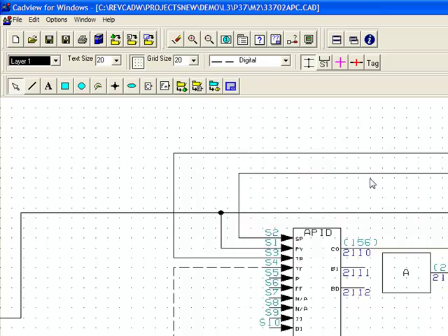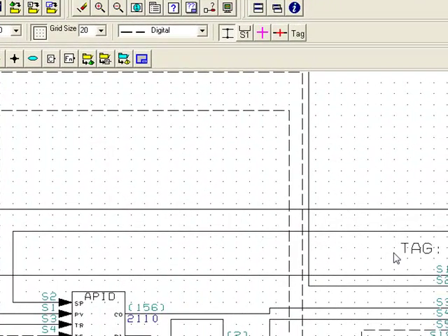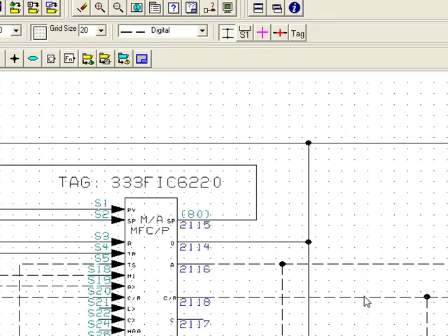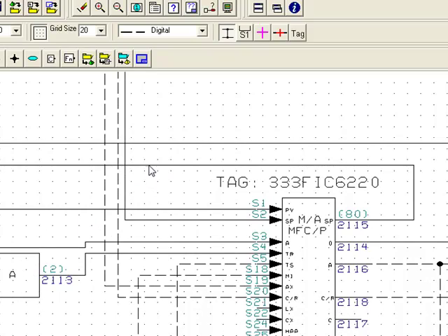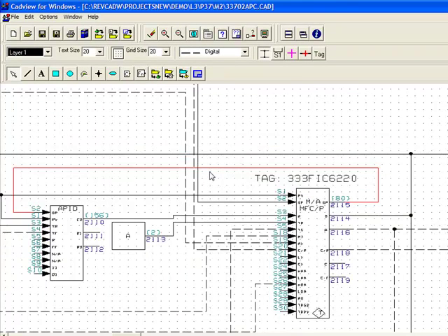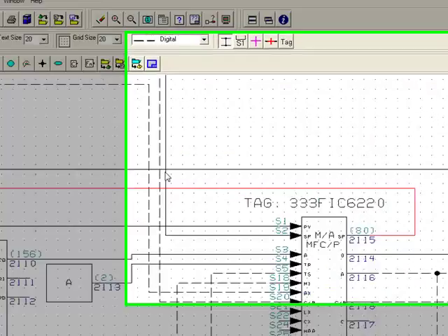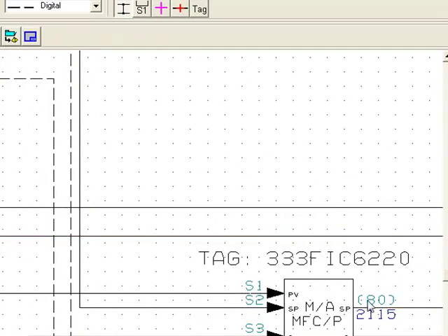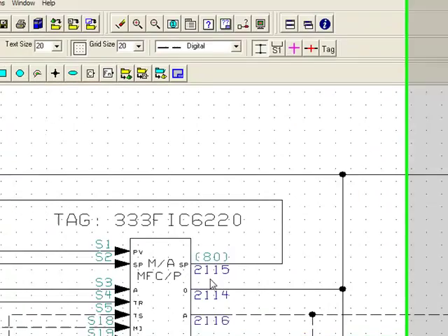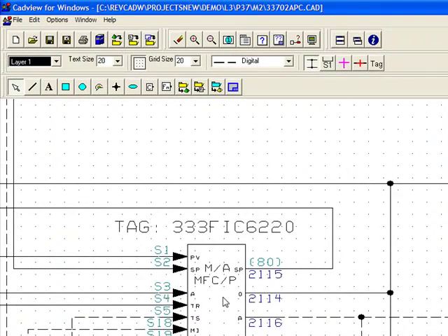So now we start to trace back through the line to see where it goes. And it goes to the output of a station block, this being the set point of the station block. So there's something going on with the line. If I identify the line, let's see if it hasn't been broken into 2 or more segments. No, if I identify the line, the whole line gets identified. So there must be something going on with the line at its origin, or the block output of the station block. So let's take a look and see what's going on.